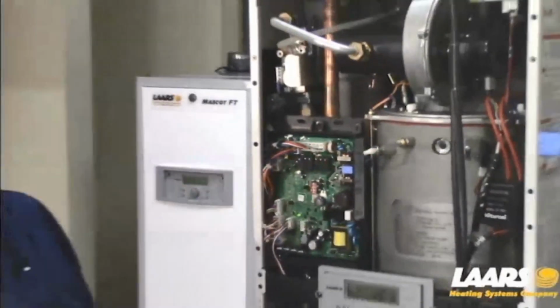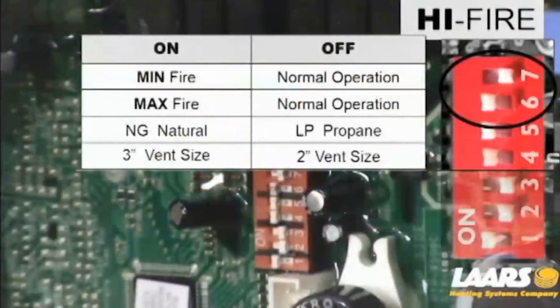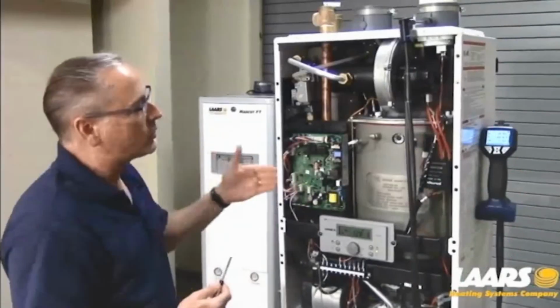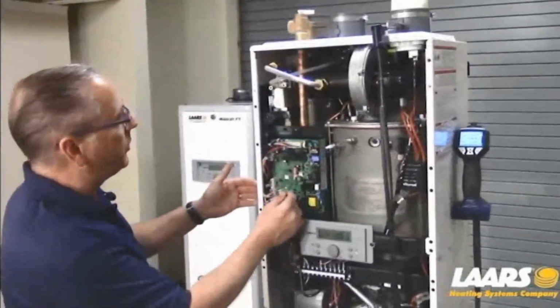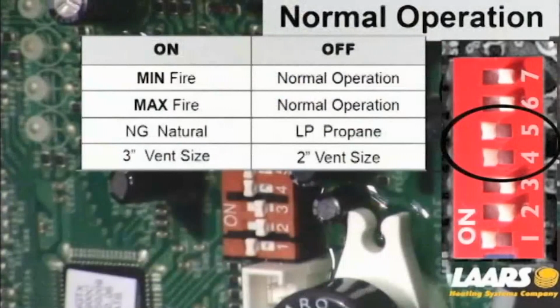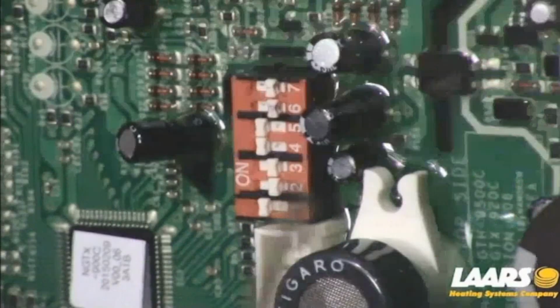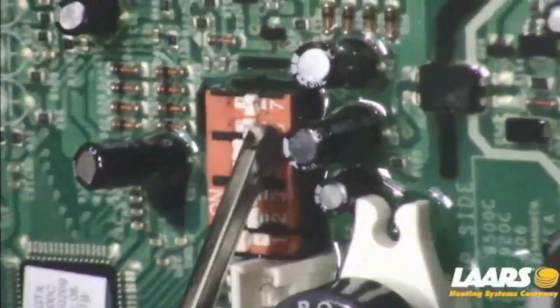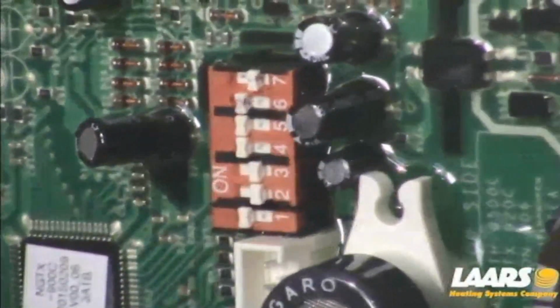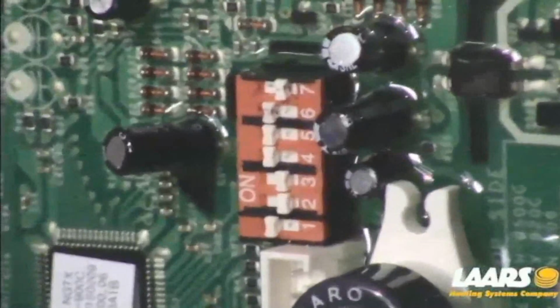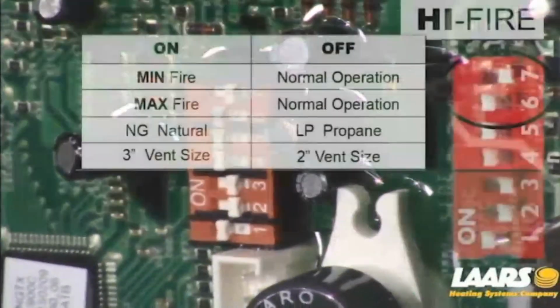Now with my analyzer installed, I want to lock the boiler into high fire. So here we have natural gas, which is dip switch 5, which is on the left-hand position or the on position. We have a 3-inch vent, which is dip switch 4, which should be the left position, which is the on position. To lock the boiler into high fire, dip switch 6, simply push that to the left-hand side to the on position, which will now lock our boiler into high fire.